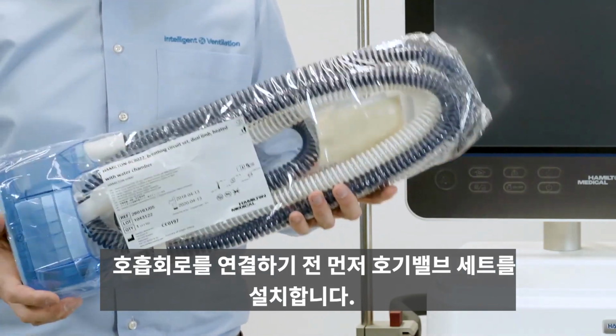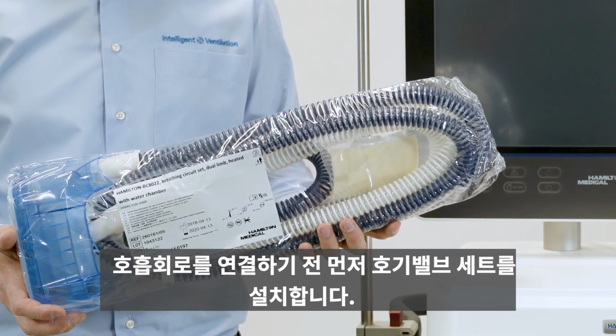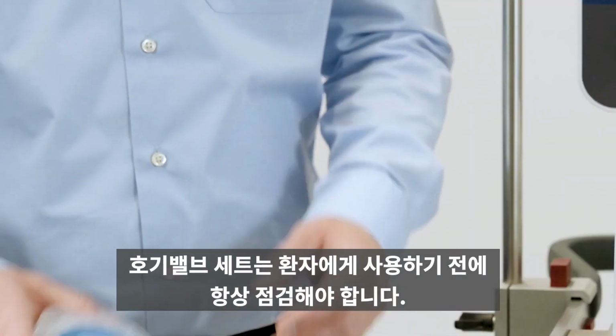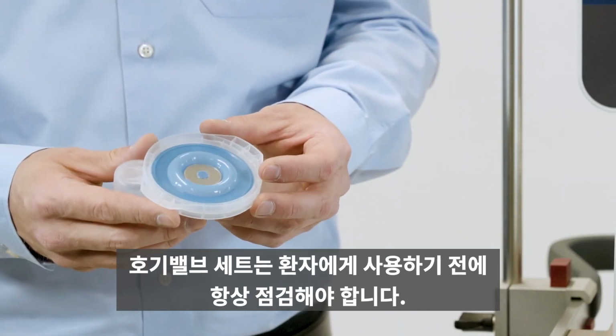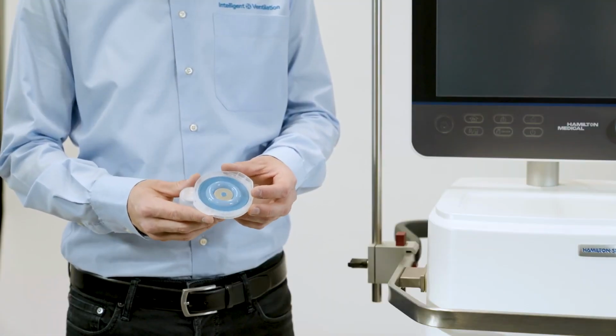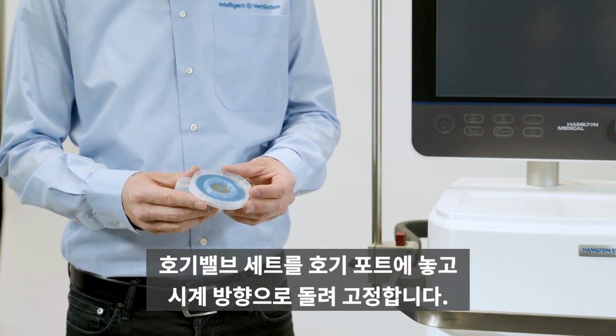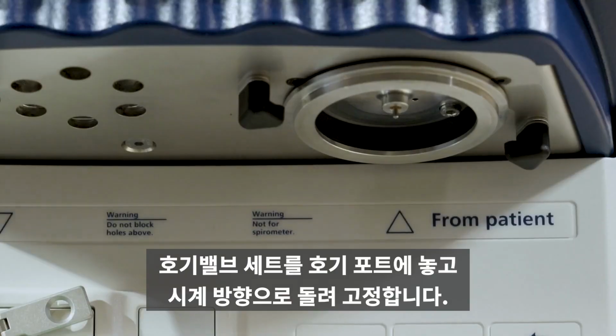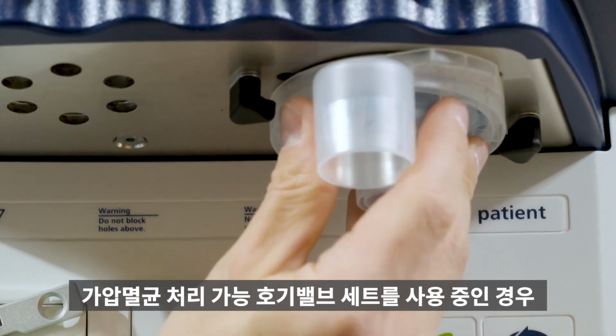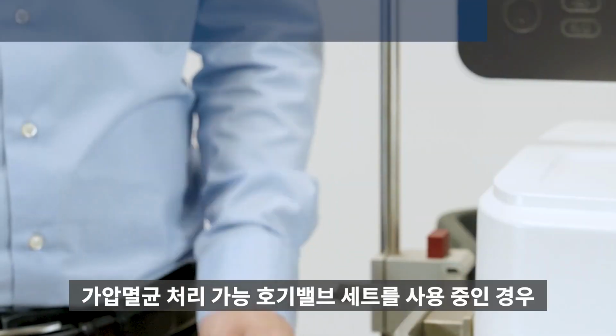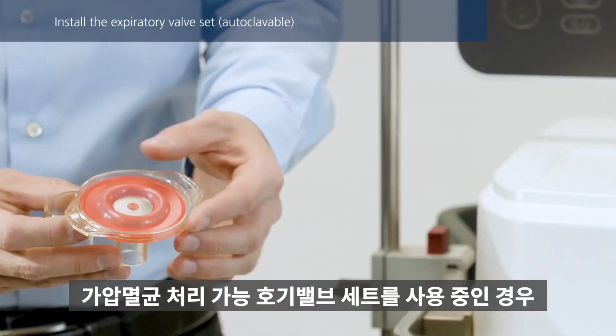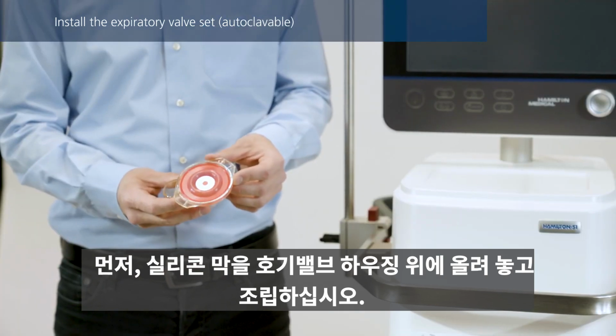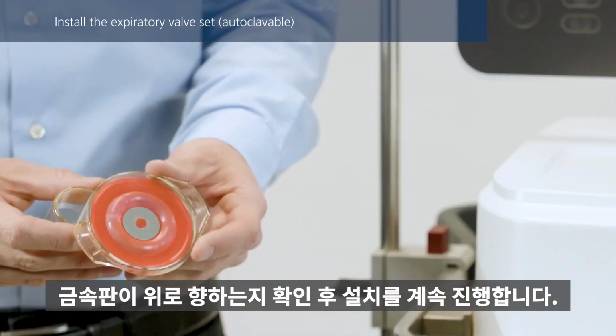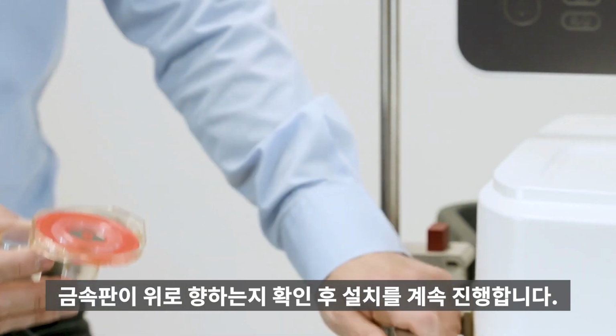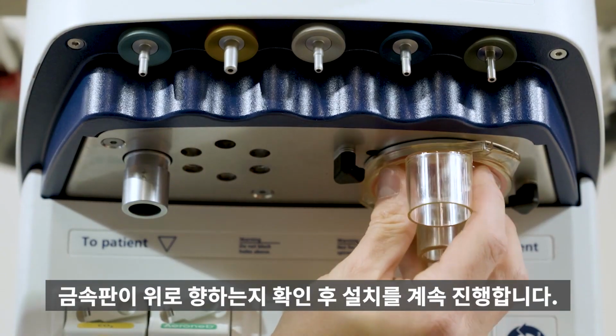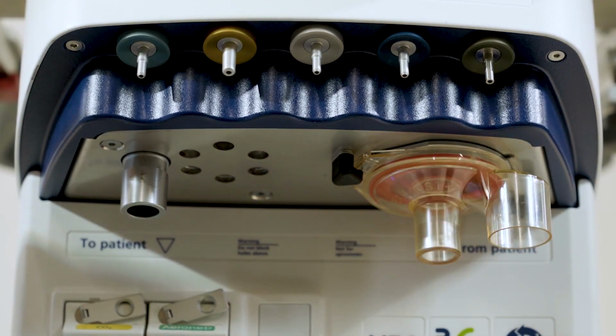If you plan on using a double-limb heated breathing circuit, start by installing the expiratory valve set. The expiratory valve set is delivered clean and ready for use. Always check the set before using it on the patient. Position the expiratory valve set in the expiratory port and twist it clockwise until it locks into place. If you are using an autoclavable expiratory valve set, first assemble it by placing the silicone membrane onto the expiratory valve housing. Ensure that the metal plate is facing upwards, and then proceed with the installation. The procedure is the same as for a single-use component.